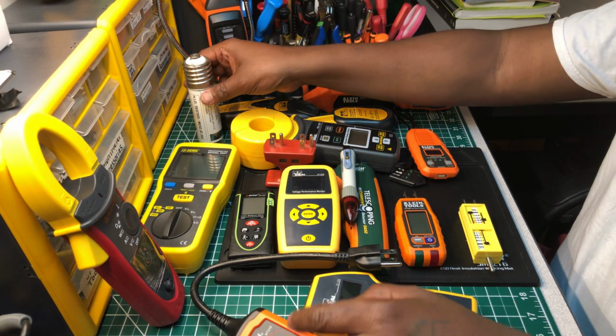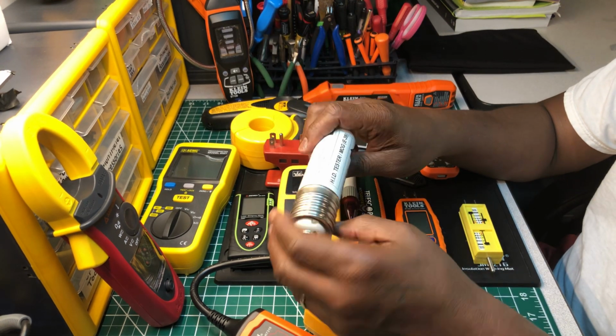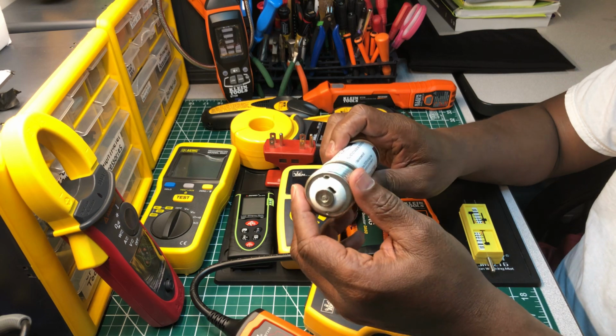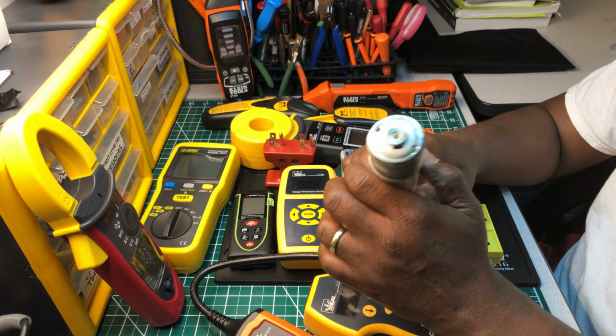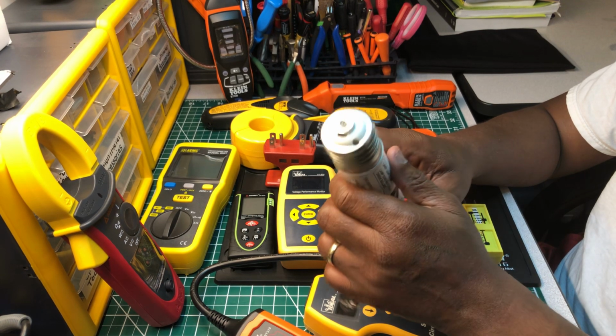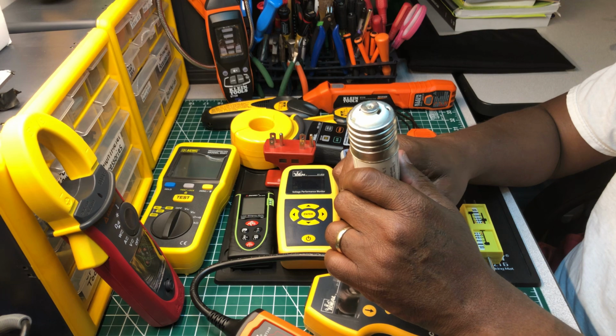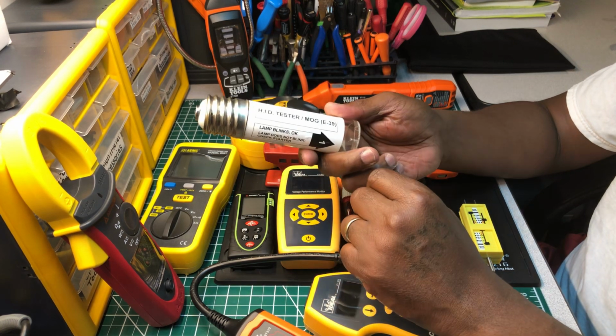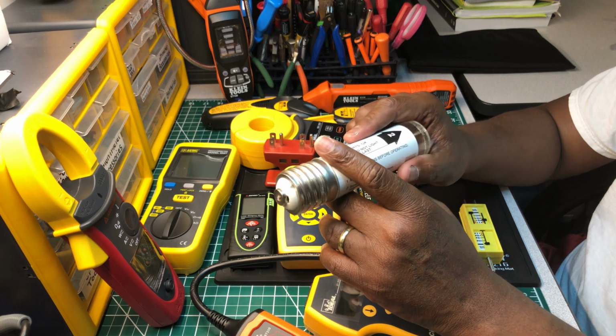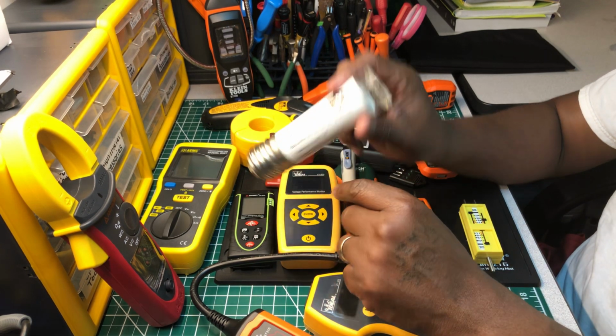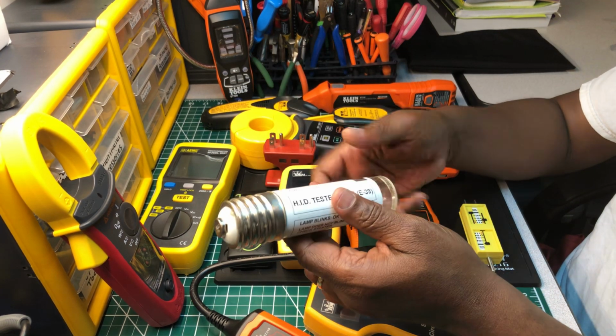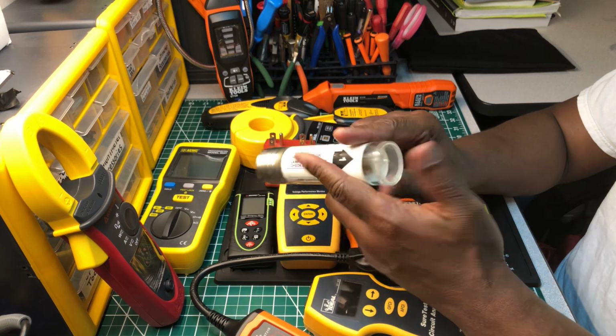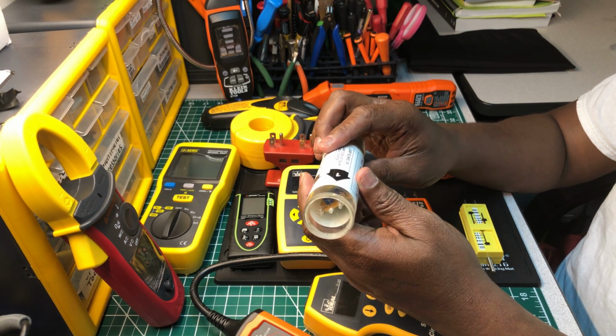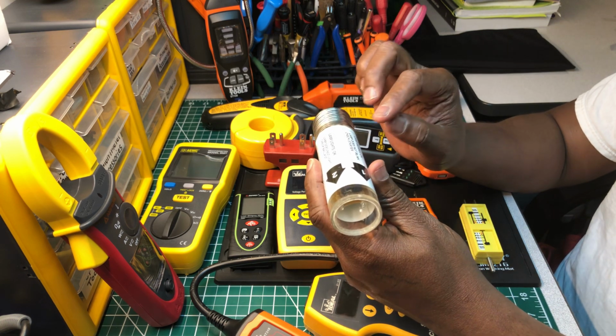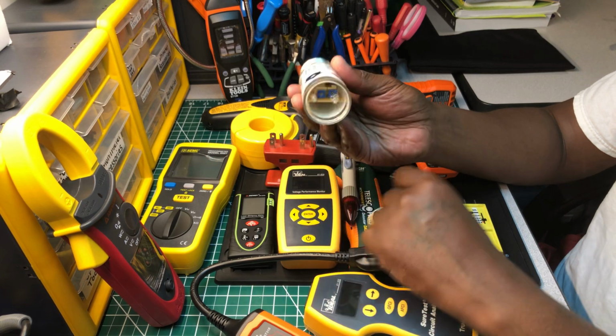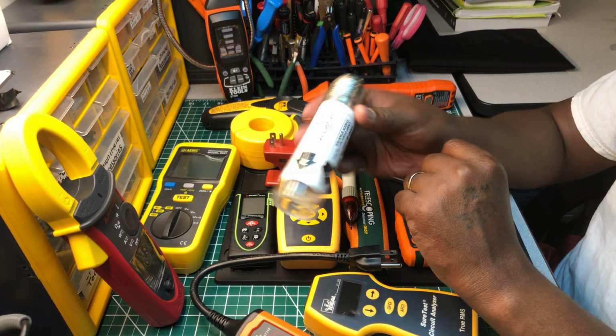Now this right here is like a ballast tester for when you're testing metal halide bulbs, the big bulbs you see outside or in warehouses, way up in the ceiling or on the side of the building. Sometimes you get in there and you don't know if it's the bulb or the transformer. You just screw this in, turn the light on or cover the photo eye, and it lights up to tell you if it's the ballast, the transformer, or the bulb. This makes your life easy when you're dealing with those types of bulbs.